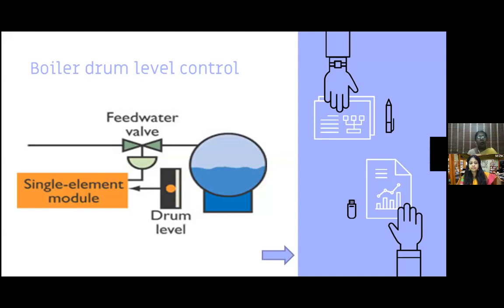So what will it do now? It receives this signal - that is, the current value of the level from the boiler - and compares it with the reference value. The reference value is nothing but the value at which we want to maintain the liquid level in the boiler. For example, I want to maintain a level at 20 meters, but the current value I'm getting from the level sensor is 25 meters.